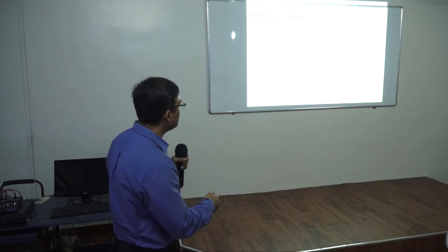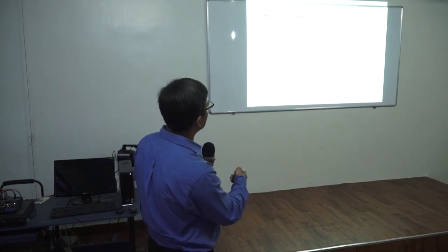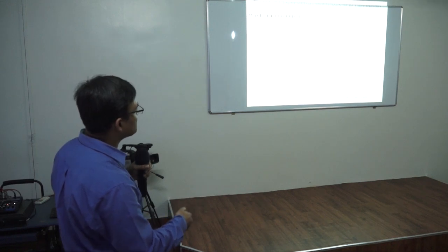Now, in my second published paper, I tried to check with speed variation what the level of fault variation, or the fault signature variation, is. These are the results for that. The red line indicates the varying fault. This is amplitude versus speed. This is the mean wavelet coefficient. Here also a drastic change is observed between the varying fault and no fault.